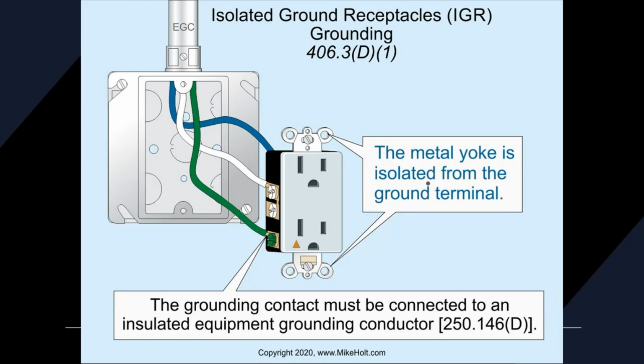Okay, the equipment ground for the yoke must be connected to the insulated equipment grounding conductor. So the regular ground is touching the yoke. Isolated ground receptacles: the grounding contact must be connected to an insulated equipment grounding conductor per 250.146(D). So this is a separate isolated ground. It's going to have a bond through this yoke going to these screws. And then it's going to have this insulated and isolated ground going all the way back to the panel, wherever that is. And it's not going to tie into the other grounds, and it's not going to tie to the bonds. It's going to get its bonding and grounding through the yoke. And this separate conductor is going to handle the clean power, the clean ground back.